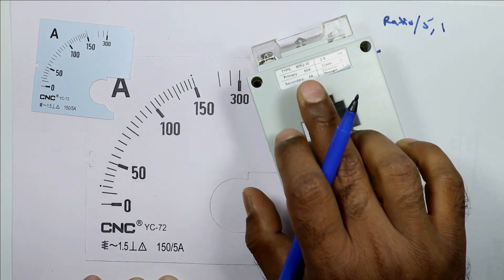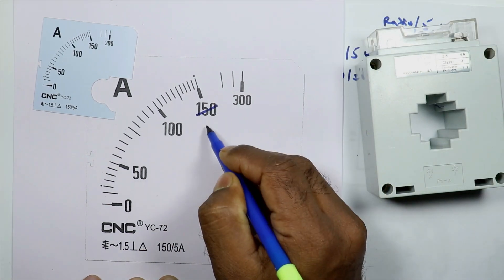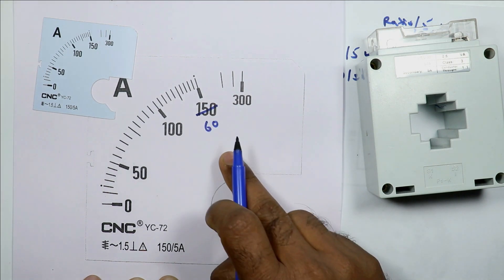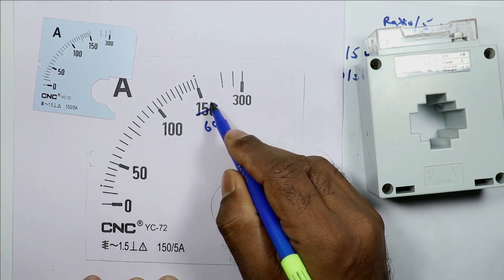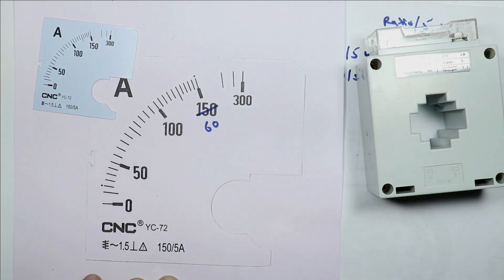Right now ratio of CT is 60, so I am writing 60 here. If pointer aims at this point then we will consider this as 60 ampere current, not 150. For the below mentioned range we need to do some calculation to change this.